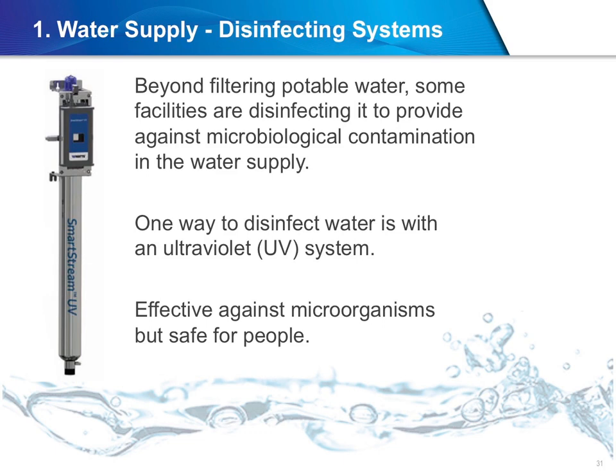Connected to a power source, they produce UV light that is projected onto the incoming water without the need for any chemicals to be handled or added to the water. For large systems, they are commonly completely enclosed for safety to prevent any accidental UV exposure to people. They also typically have sensors indicating their use and performance levels, and can be specified to operate efficiently by only turning on when there is actual water flow in the supply line.